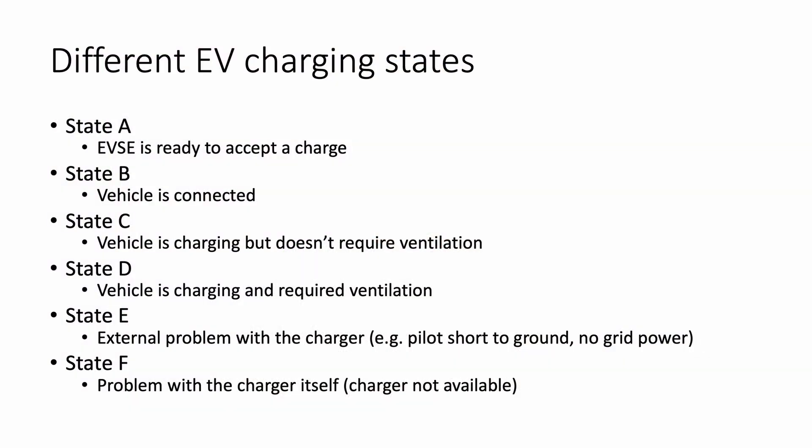The charger itself can have about six different states, labeled A to F. State A means the device is ready to charge. When we plug in the cable, the device detects it is connected to a car and switches to state B. When the car is charging it will be either state C or state D — D requires ventilation of the charging area, C does not. States E and F indicate errors: E is an external error, and F is a fault in the device itself.